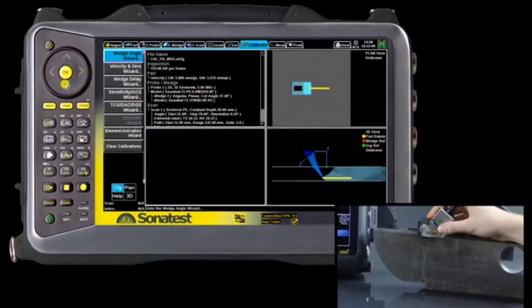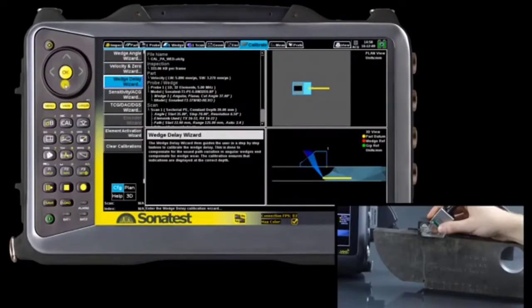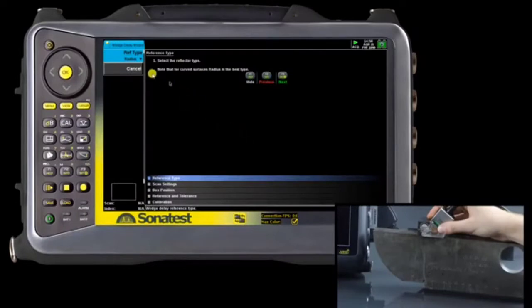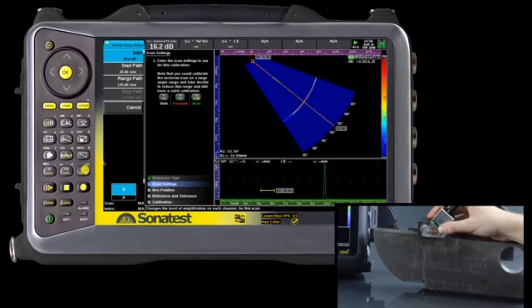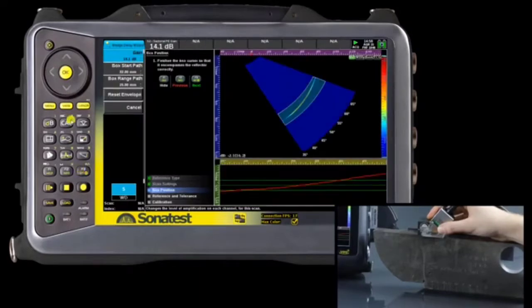We are going to select the wedge delay wizard. It is possible to do the calibration on a different reflector, but for this block, the radius is the best one to use. As always, we will get better results with unsaturated signals. We suggest to put it around 80% full screen height. The signal should be within the extraction box border.